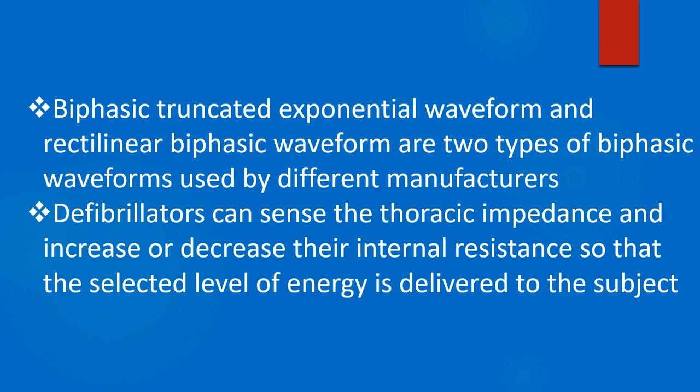Defibrillators can sense the thoracic impedance and increase or decrease their internal resistance so that the selected level of energy is delivered to the subject.